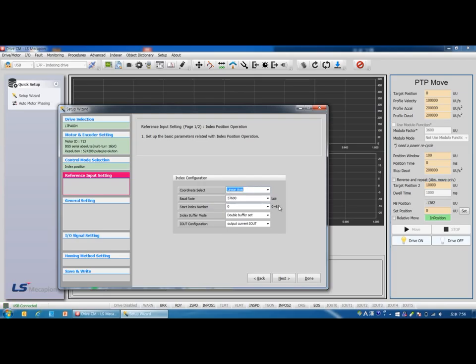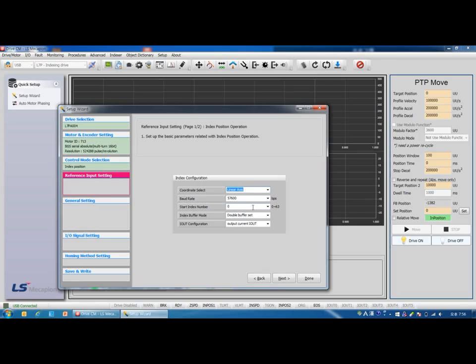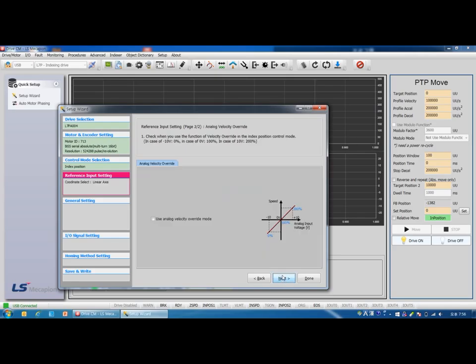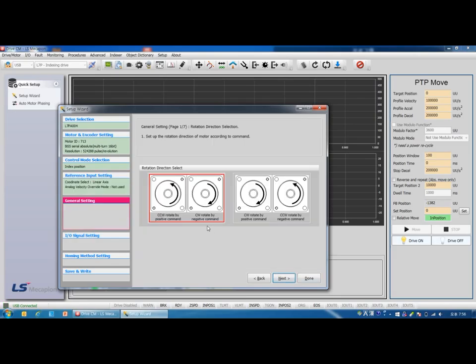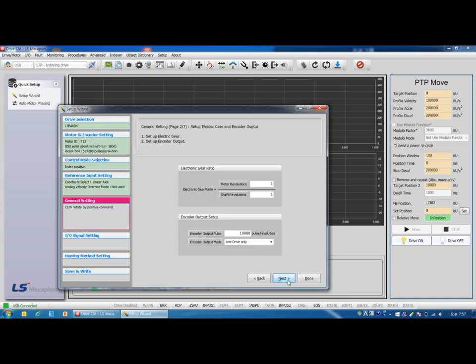Baud rate. If using host controller through Modbus communication, set baud rate. This is the setting for start index number, which is 64, operated by digital input signal IC0 to IC5. Next. This is analog velocity limit. For this case, we are not using this function, so next.